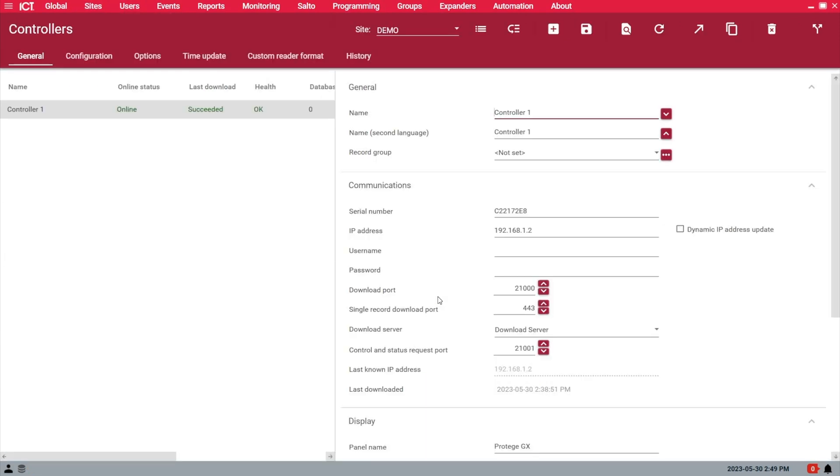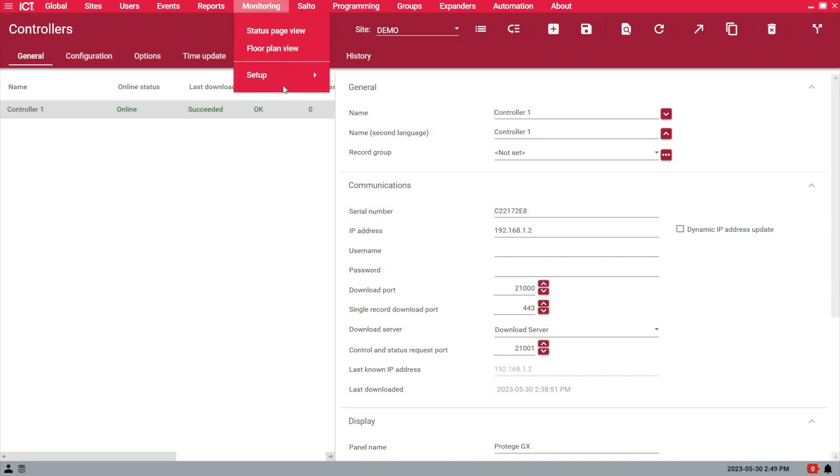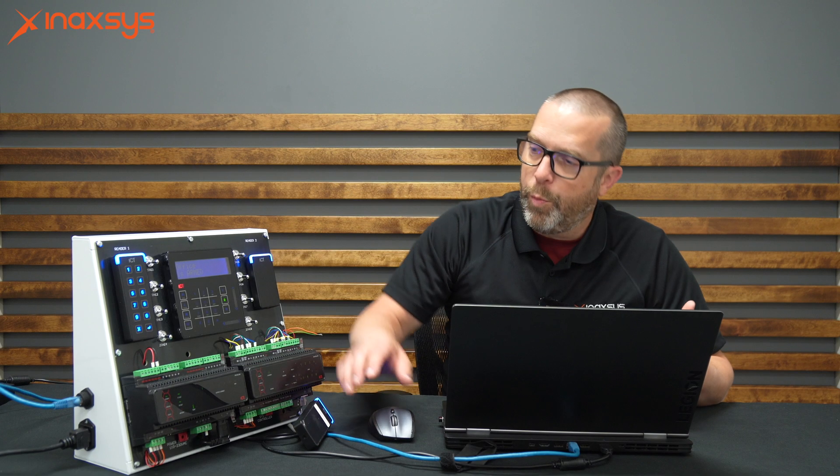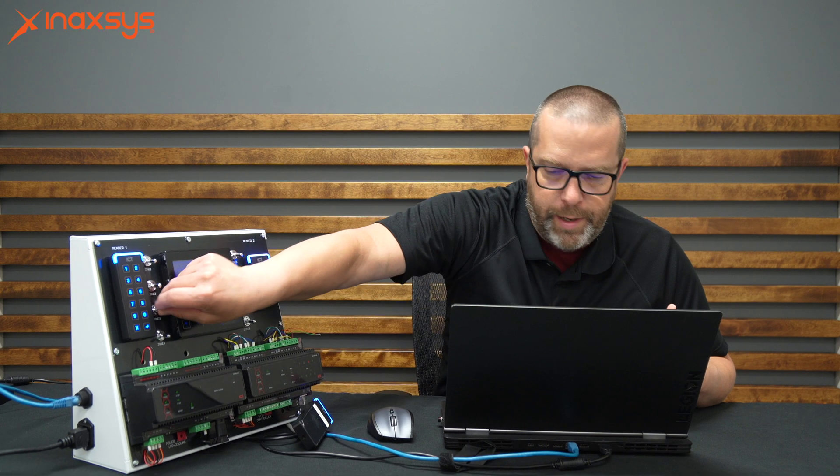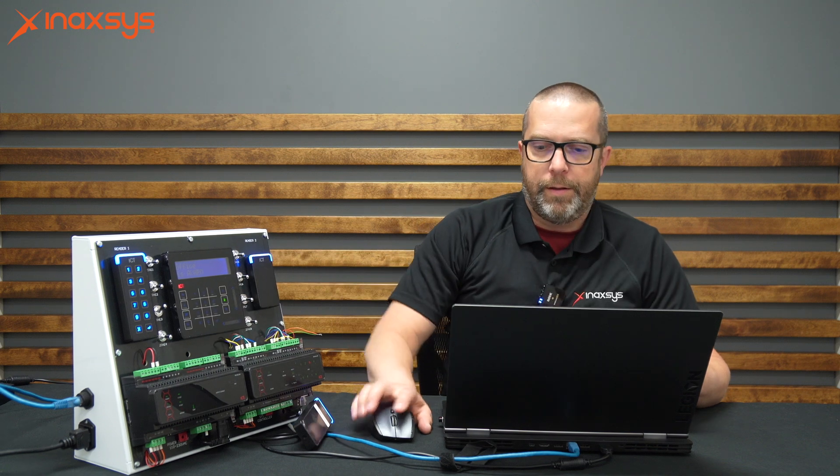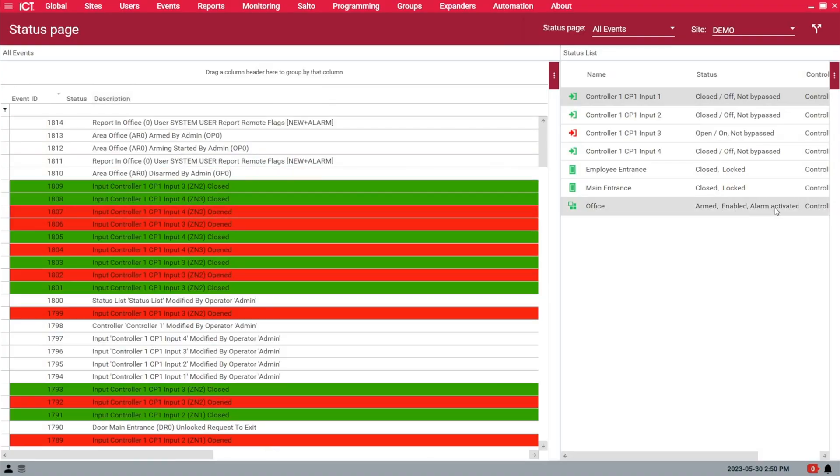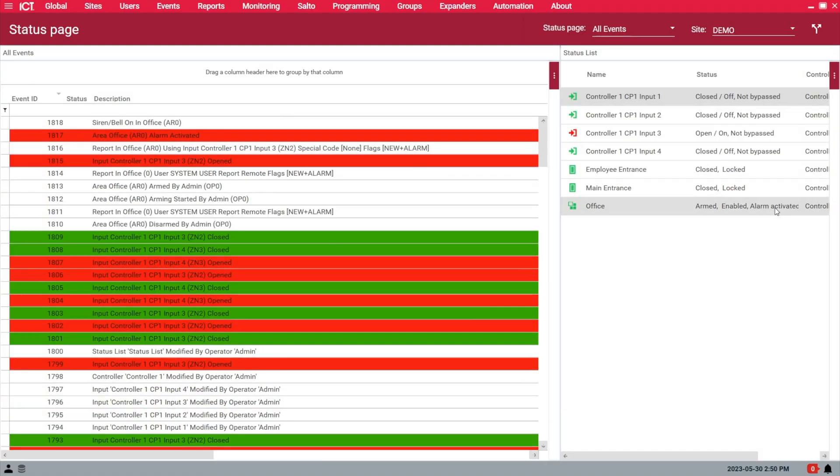I can go back to my controller - actually, it's already okay and the health status shows okay now. So now if I go back to my monitoring page, if I open zone 3, it's an instant zone now, and you can see the system is in alarm.